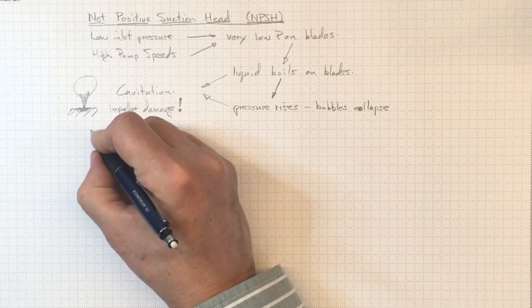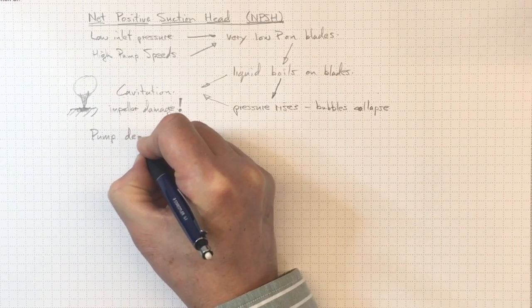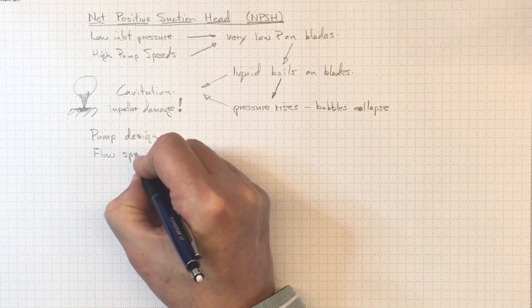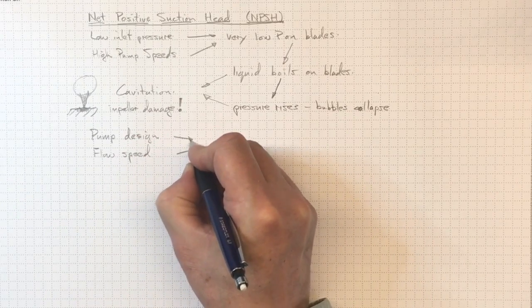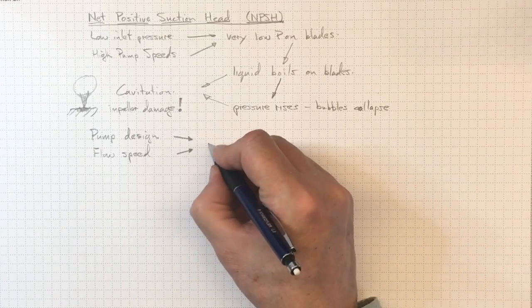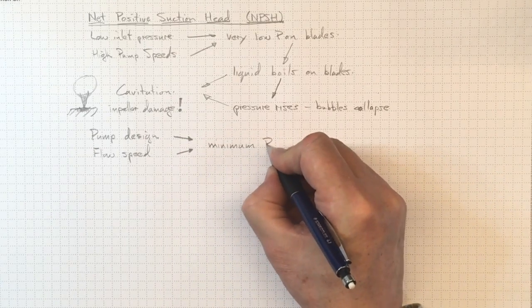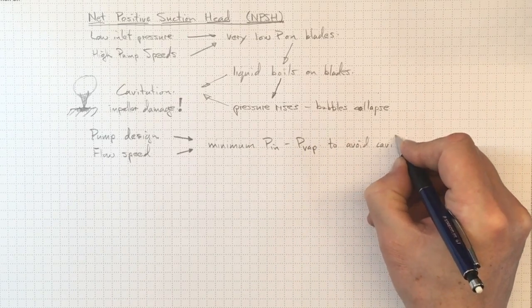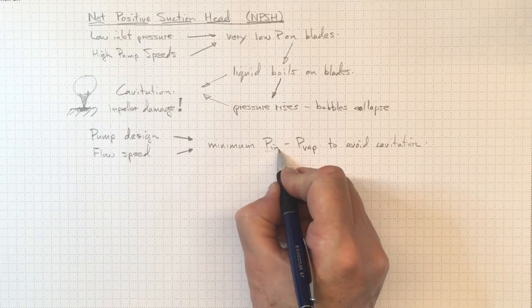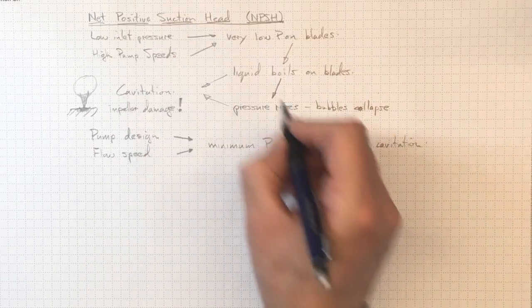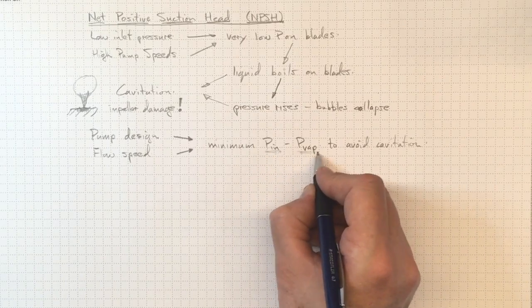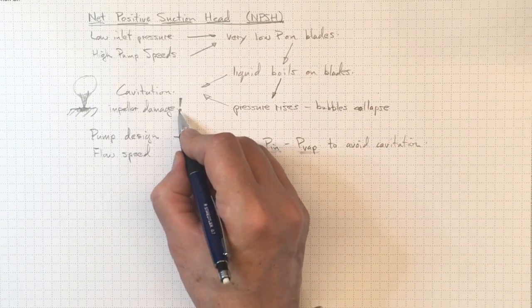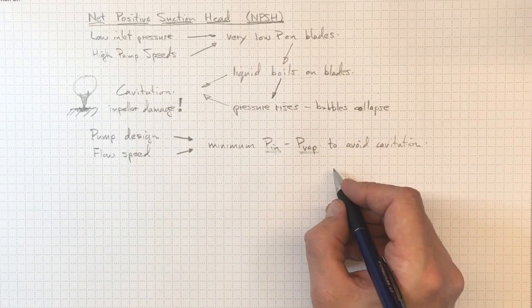So as a consequence of pump design, in order to get the performance that we're looking for and the flow speed of the liquid going through the pump, the two of those in combination will result in a minimum inlet pressure that we can tolerate compared to the vapor pressure in order to avoid cavitation. So if we can just keep the inlet pressure or the suction pressure enough above the vapor pressure, then we won't have any boiling and we won't have any bubbles collapsing. We won't have any cavitation and we won't have any cavitation damage.